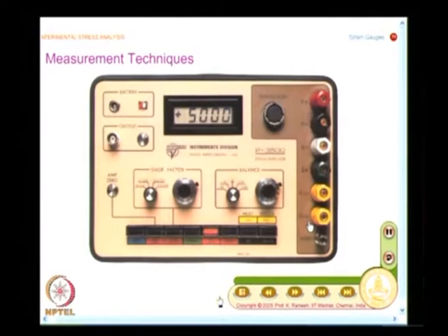In one of the earlier classes we have looked at, when you are using a Wheatstone bridge, to maximize the signal from the Wheatstone bridge, I should use R1, R2, R3, R4 having the same values. Strain gauges are available at 120 ohms and 350 ohms very commonly, and depending on the strain gauge that you select, you must also have the other resistors selected in the Wheatstone bridge.